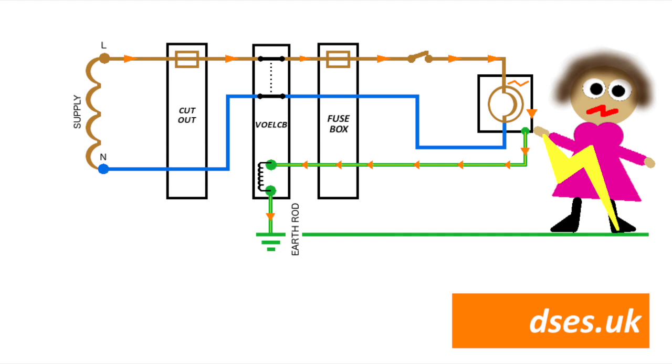So steps would presumably have to be taken to isolate this pipe work from earth. Although the installation I removed this device from had a bonded metallic gas pipe, which again means that in the event of a fault, the fault current may have been through the gas pipe work and not through the rod, leaving this device impotent.